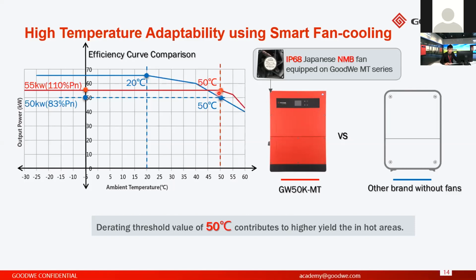decrease the AC output. So I think this is very important for the Sri Lanka customers, because in Sri Lanka, the whole year is very hot, especially in the summer. In the summer, the temperature can reach up to 45 or 48 degrees. So if you use another brand like this one, the inverter starts derating from 20 degrees. So if the temperature is 50 degrees, the inverter output will decrease a lot. So you can check this blue curve. But here, the red curve is our product. So if the temperature is lower than 50 degrees, the inverter can work normally without derating.